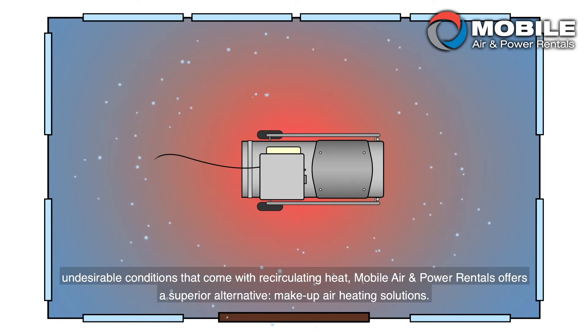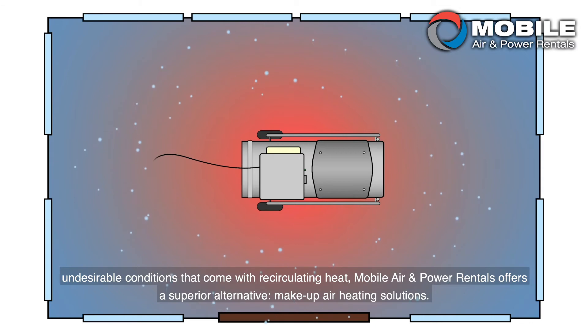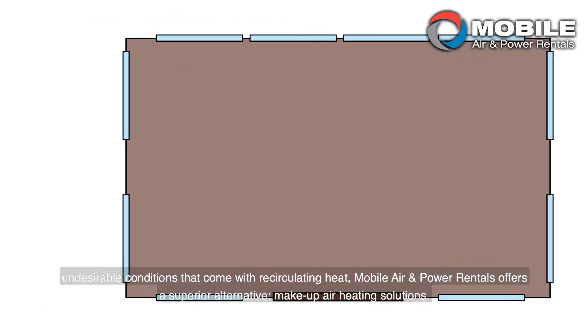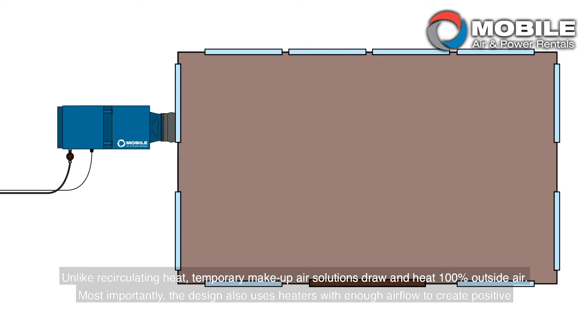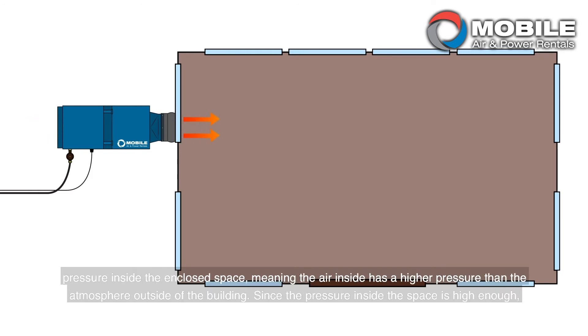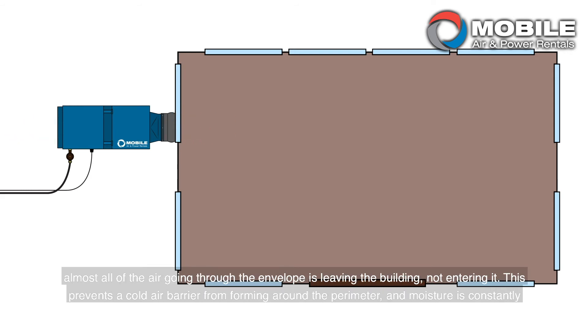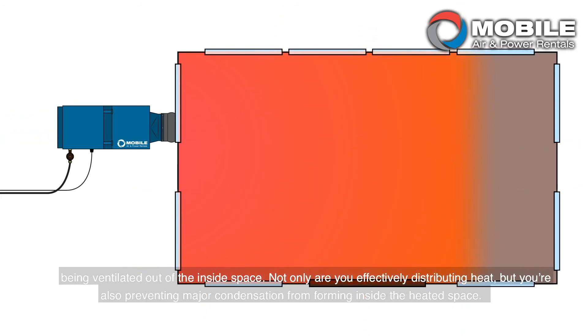To avoid the potentially undesirable conditions that come with recirculating heat, Mobile Air and Power Rentals offers a superior alternative: make-up air heating solutions. Unlike recirculating heat, temporary make-up air solutions draw and heat 100% outside air. Most importantly, the design also uses heaters with enough airflow to create a positive pressure inside the enclosed space, meaning the air inside has a higher pressure than the atmosphere outside. Since the pressure inside is high enough, almost all of the air going through the envelope is leaving the building, not entering it. This prevents a cold air barrier from forming around the perimeter, and moisture is constantly being ventilated out. Not only are you effectively distributing heat, but you're also preventing major condensation from forming inside the heated space.